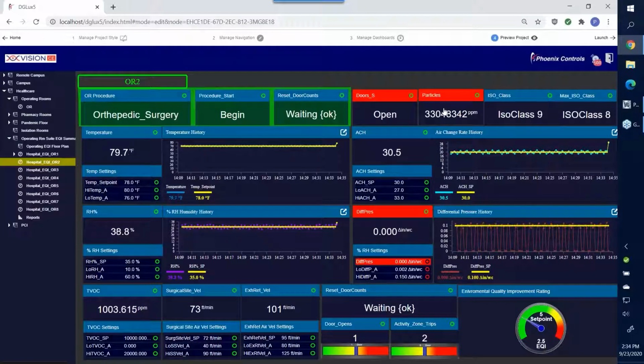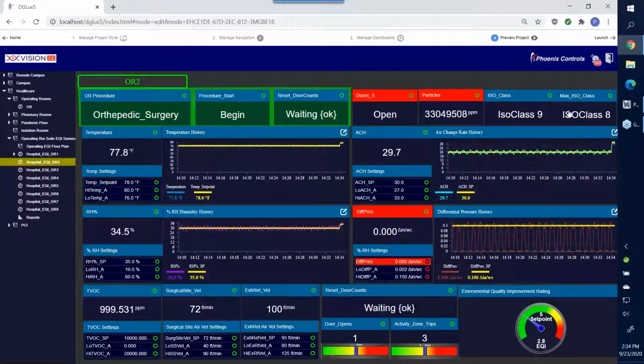The lower the particles, the more clean the operating room, and that's typically tied to an ISO classification. In this case, we're giving you what the classification is for a particular operating room, and you can see the set points change based on the procedure and/or the doctor. So again, we're not only setting the system for its operation using the accuracy and repeatability of the Phoenix valves, but now we're able to validate, providing a very simple method.